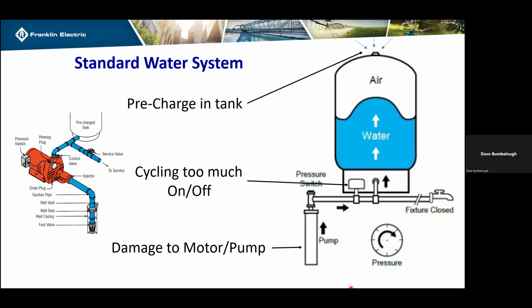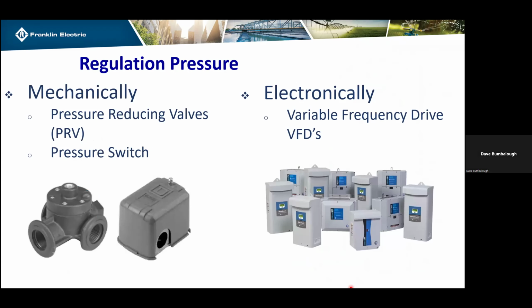We've got some kind of leakage going on because the system was allowed to cycle too much, damaging the wire, either the drop cable and/or the windings inside the motor, and it's allowing that voltage to seep out through the shell and basically energize most of your metal parts or even earth, ground. That can also be carried through the ground. Animals are more sensitive to anything when that particular problem pops up, whether it's some kind of mechanical device or electronic device. We've got to be very, very careful there that we identify those leakage voltage situations.